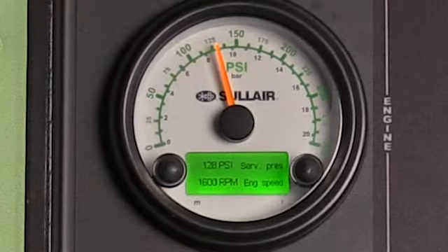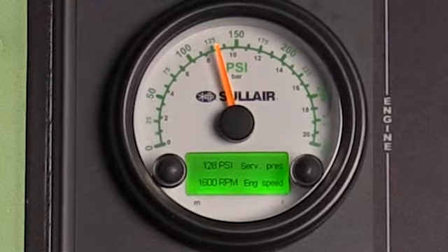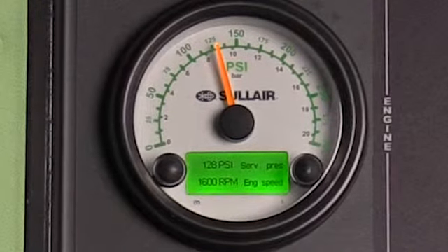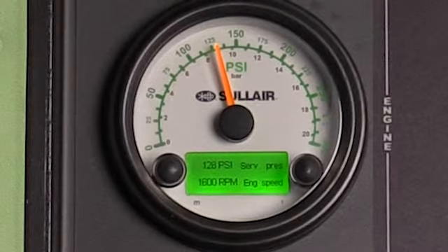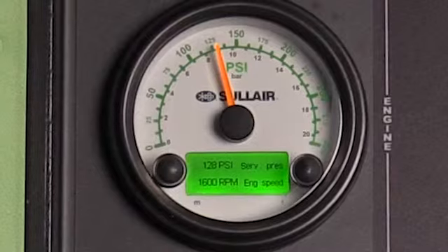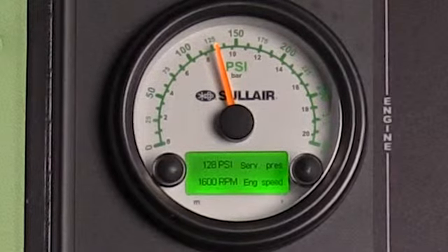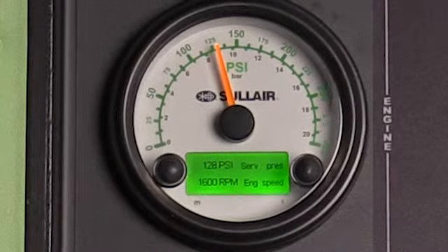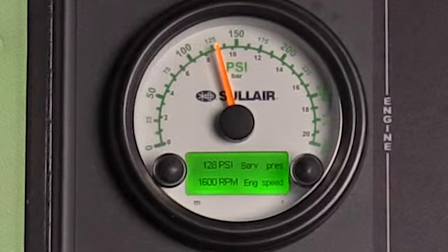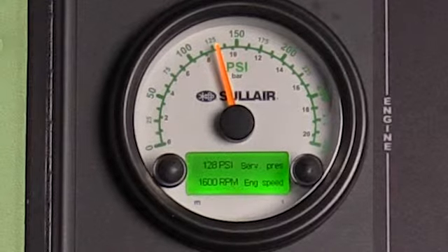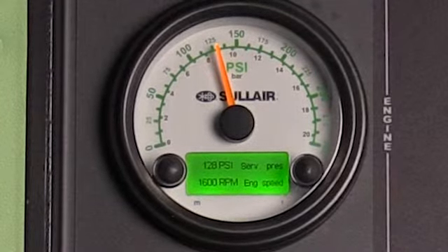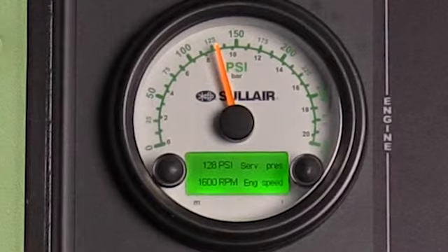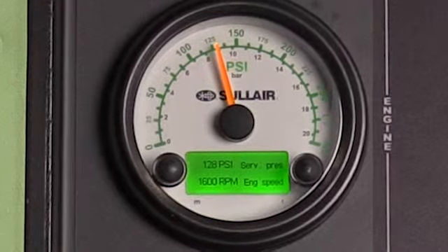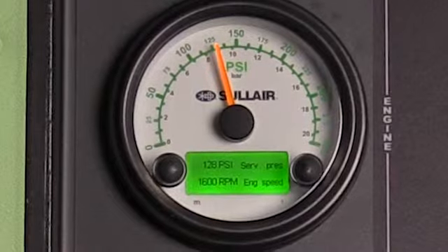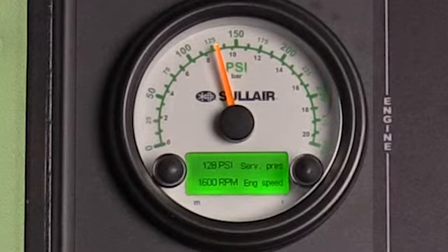What we would like to demonstrate is the 3 states a compressor will be running in: unloaded, modulated, and loaded. We will start off with unloaded. With the ball valve closed, what we're simulating here is the operator having all of his equipment turned off with no load being asked of the compressor. At this point, the compressor has reached its unload pressure settings. This will cause the engine idle to drop to minimum and the inlet valve to close.